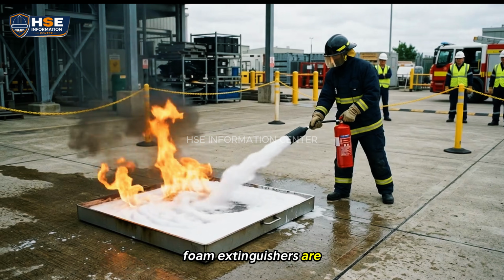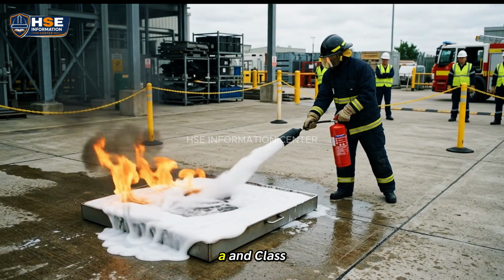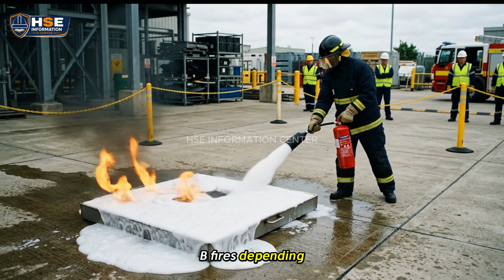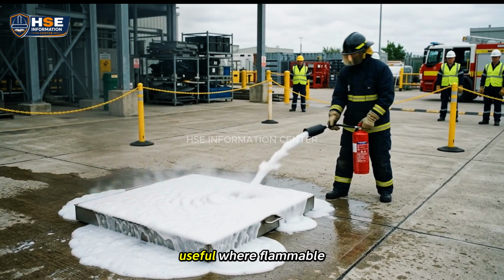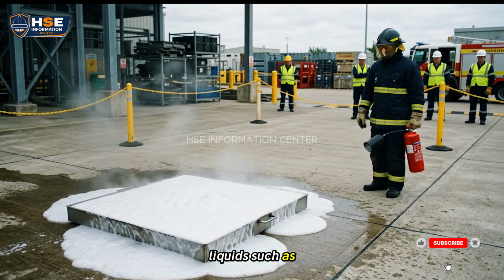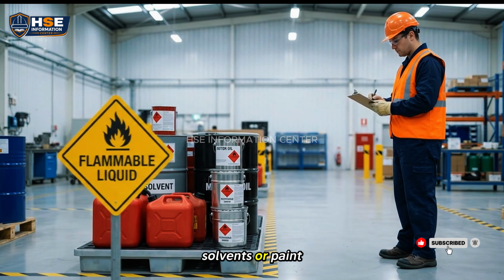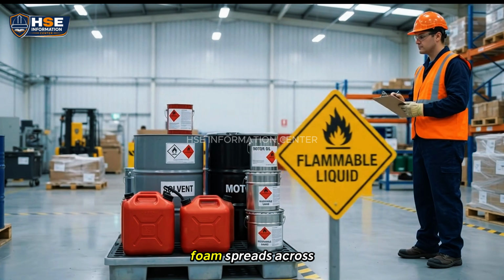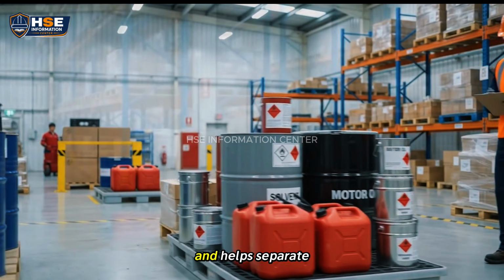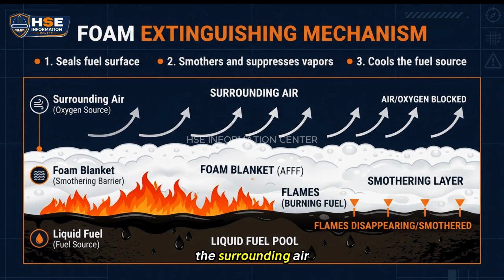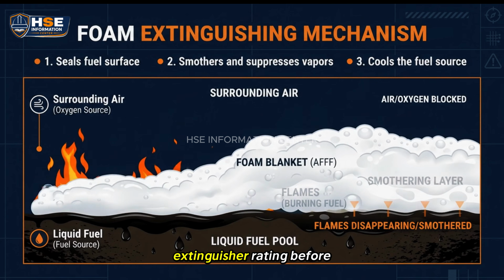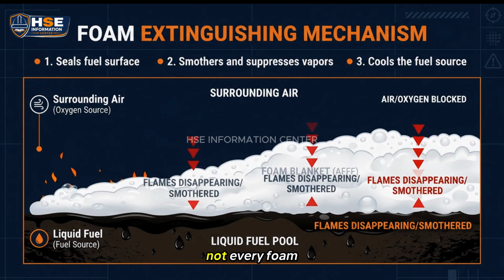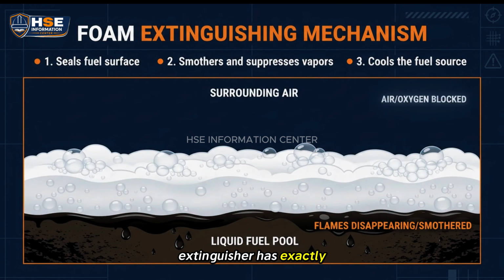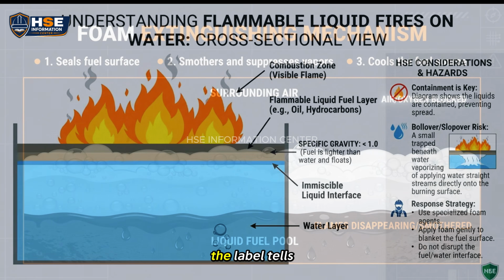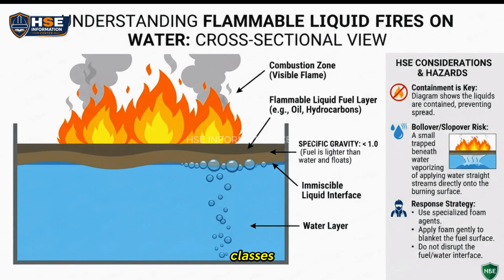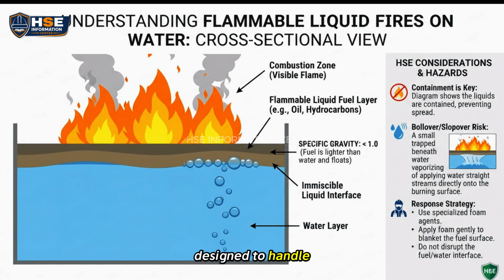Foam extinguishers are commonly associated with Class A and Class B fires, depending on their rating. They can be useful where flammable liquids such as fuel, oil, solvents, or paint are involved. Foam spreads across the liquid surface and helps separate the fuel from the surrounding air. Always check the extinguisher rating before use. Not every foam extinguisher has exactly the same application. The label tells you which fire classes the extinguisher is designed to handle.